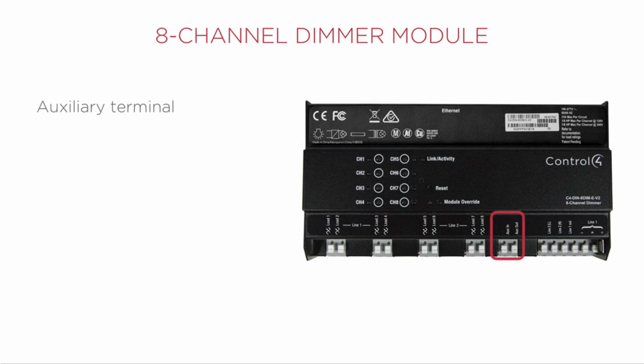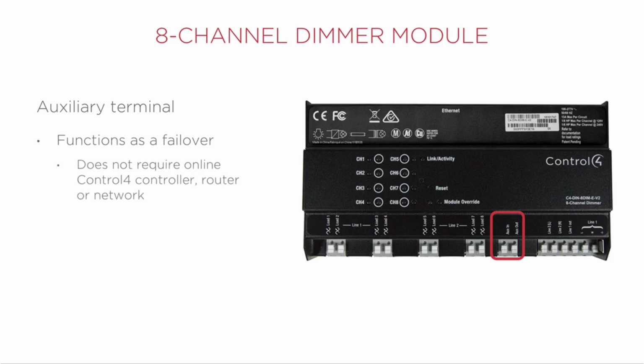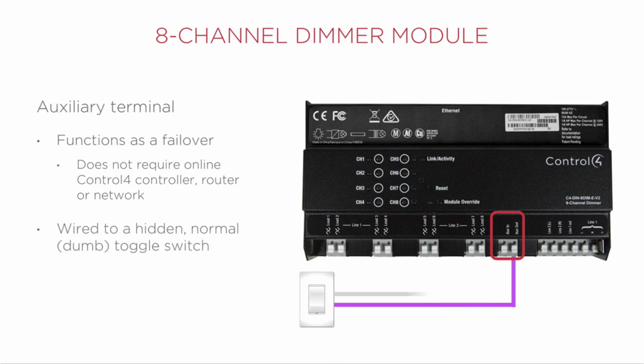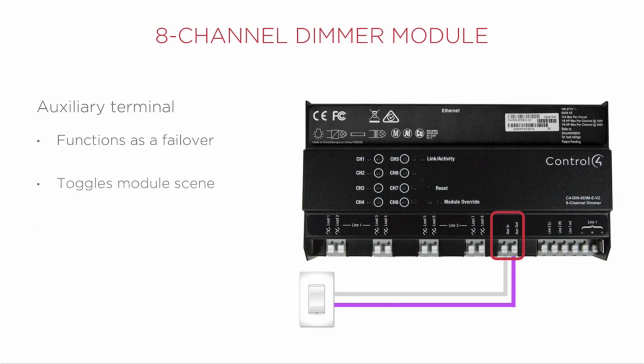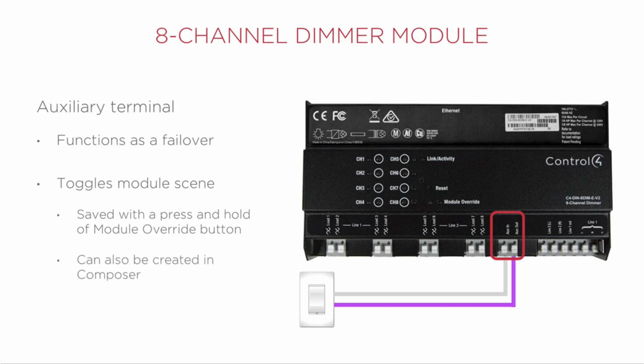There is an auxiliary terminal that can be used for failover modes. This failover does not require a Control4 controller, a router, or even a network connection. This terminal is wired to a hidden, normal, dumb toggle light switch. That light switch would toggle the module scene that was saved with the module override button. That scene can also be created in Composer.